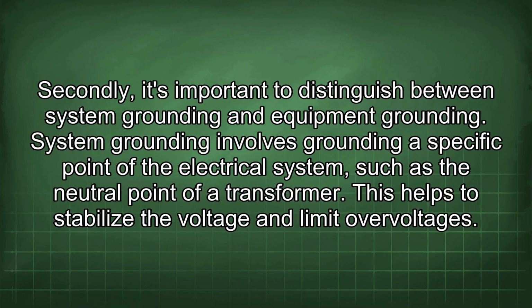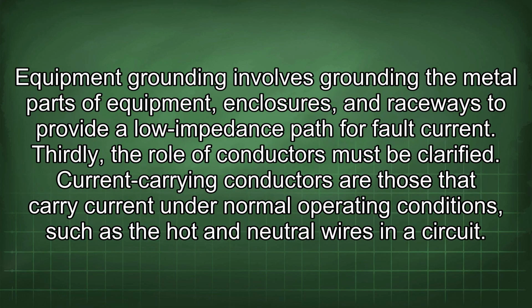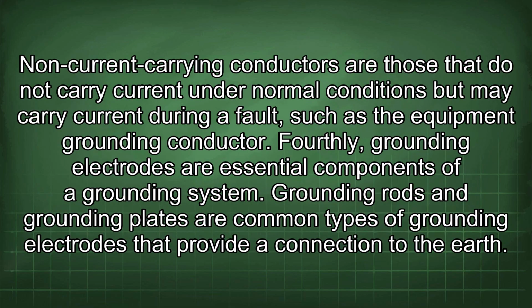Secondly, it's important to distinguish between system grounding and equipment grounding. System grounding involves grounding a specific point of the electrical system, such as the neutral point of a transformer. This helps to stabilize the voltage and limit overvoltages. Equipment grounding involves grounding the metal parts of equipment, enclosures, and raceways to provide a low impedance path for fault current. Thirdly, the role of conductors must be clarified. Current-carrying conductors are those that carry current under normal operating conditions, such as the hot and neutral wires in a circuit. Non-current carrying conductors are those that do not carry current under normal conditions, but may carry current during a fault, such as the equipment grounding conductor.